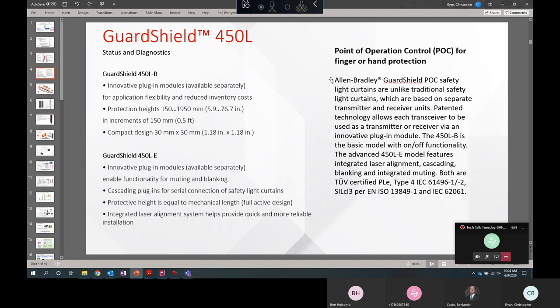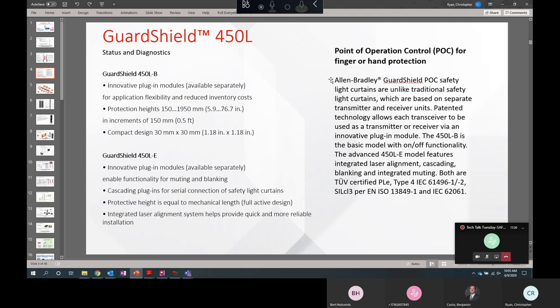So the light curtain comes in two different versions, two platforms. We have the 450LB. Think of B for basic. That has on-off functionality. And then we have the 450LE. Think of E for enhanced for applications that require blanking, muting, or cascading. The two 450L versions have no difference in their cross section, protective height, resolutions, that's 14 millimeter or 30 millimeter spacing between the laser beams. The enclosure ratings are both IP65 and your operating and storage temperature and mounting options are all the same.